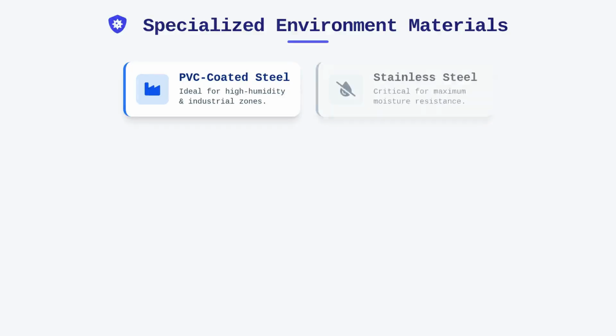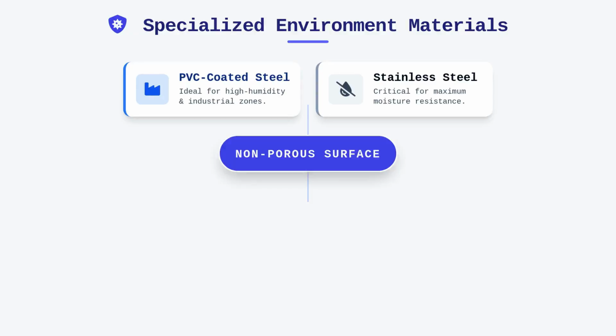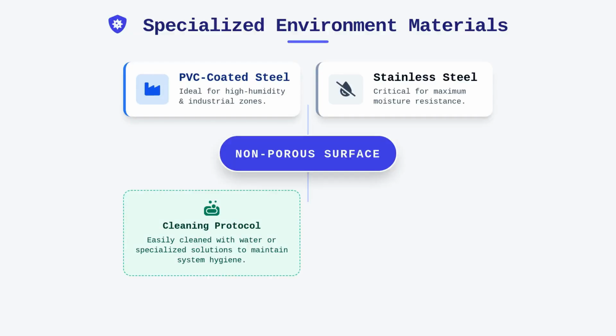Specialized environments require us to move beyond standard materials and consider coatings that dictate how we handle microbial growth or chemical exposure. PVC-coated steel and stainless steel are frequently found in industrial applications or high humidity zones where moisture resistance is critical. These materials are generally non-porous, which makes them easier to clean extensively with water or specialized solutions, provided you respect the limitations of the coating.